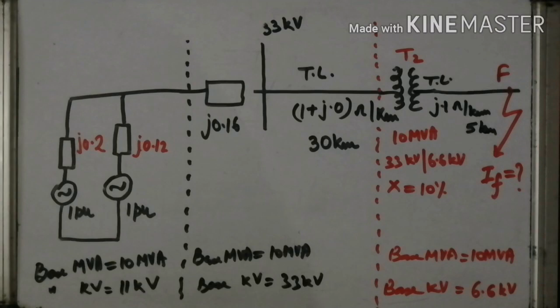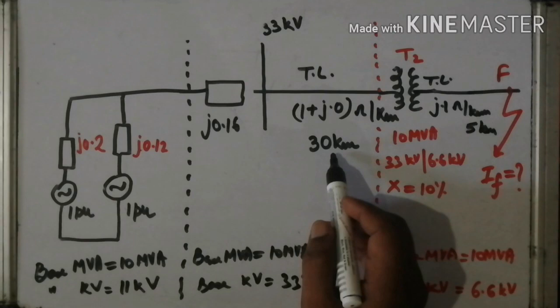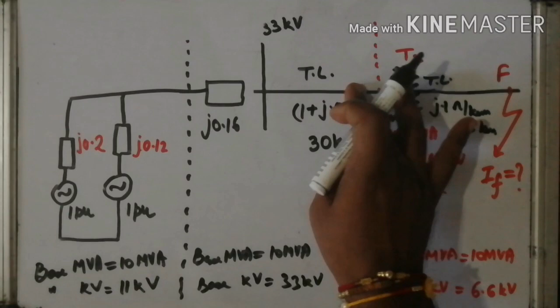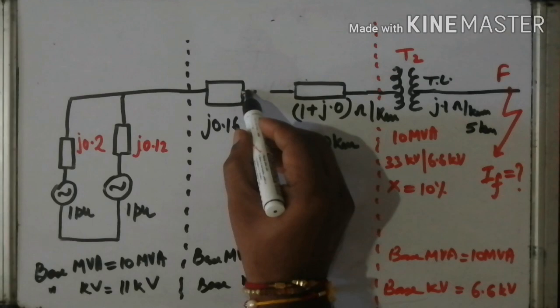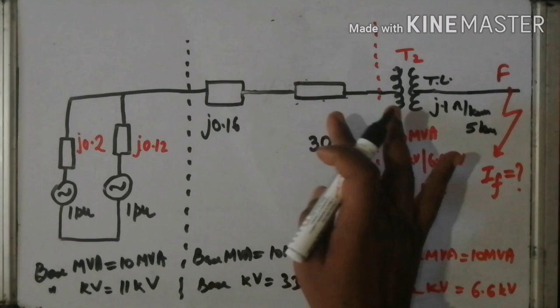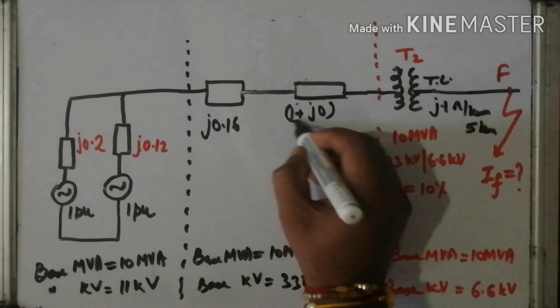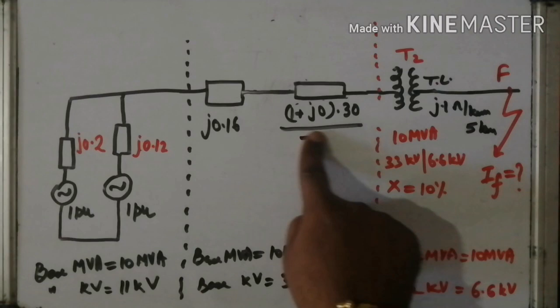Here TL is given. Its impedance is 1 plus J0 ohm per kilometer. First of all, I am going to multiply this with the kilometers, that is 30 kilometer, and divide it by the base value, that is Z base. It will look like this, that is impedance 1 plus J0 into 30 divided by Z base. We know that the value of the Z base is nothing but kV base square divided by S base. So kV base is 33, the square of 33 divided by S base, that is 10. Right? Formula is Z base is equal to kV base whole square divided by S base. According to this formula, this one is over here.